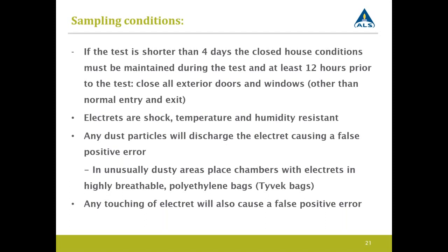The electrets are shock, temperature and humidity resistant. Any dust particles will discharge the electret, causing a false positive error. In unusually dusty areas, place chambers with electrets in Tyvek bags. And any touching of the electret will also cause a false positive error. So it is not advised to remove the electret from the chamber, because it is very easy to touch it, or a speck of dust could fall on the electret, causing the false positive error.